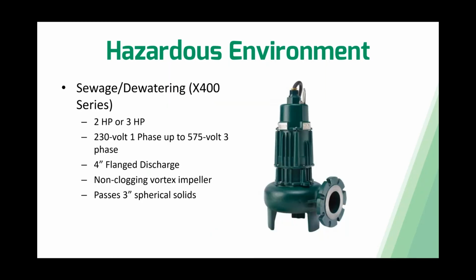So going bigger in the sewage and dewatering section of explosion-proof pumps, we have the X400, which is the X404 and the X405. The 404 is a 2 horsepower. The X405 is a 3 horsepower. Voltage is a little bit different here as the pumps are getting bigger. We're not offering the 115 volt single phase here. We do offer 230 volt single phase up to 575 volt 3 phase. The discharge here for this sewage, whereas the other ones we just talked about in the X280 and 290 are 2-inch and 3-inch, this is a 4-inch flange discharge, as you can see in the picture there. Regarding the impeller, it also is a non-clogging vortex impeller. And with the X400 series, it can pass 3-inch spherical solids.